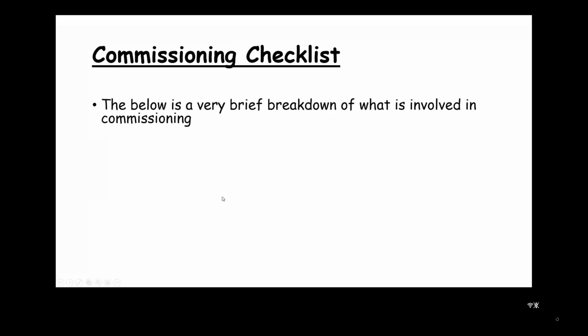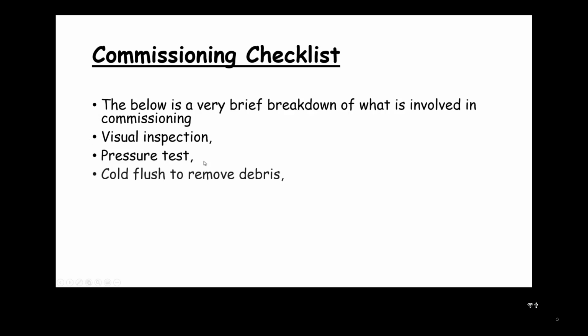Okay. So, a brief breakdown of what's involved in commissioning. Firstly, you do a visual inspection of the system and pipework. Check that there's nothing obviously wrong visually. You then carry out a pressure test, a soundness test. Which soundness test you carry out would depend on whether it's a rigid pipe system made of metal, a plastic pipe system, or a combined system of some metal and some plastic. Once you've done the pressure test, you then do a cold flush to remove any debris from the pipework.